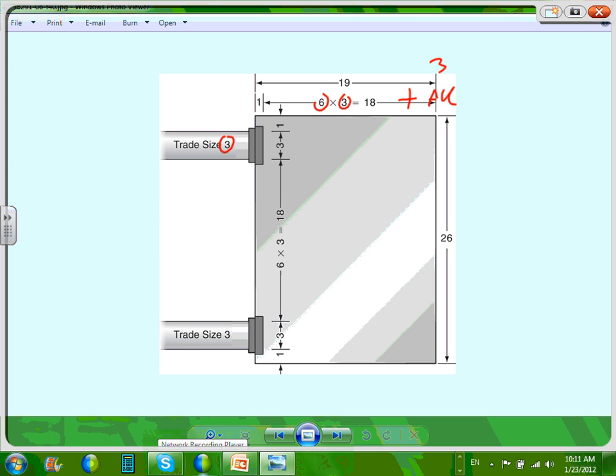Okay, angle with splices, and so on. 6 times the largest diameter of the largest raceway in the same row. The distance shall be increased for additional entries by the amount of the sum of the diameters of all other raceway entries in the same row on the same wall. Yeah, you have to add a 3 for this one, guys, because there's no conduit here, so they'll give you a 3. They'll give you what, 18 plus 3 is what, 21? 21 inches. And then the distance between the conduits is always 6 times the largest conduit.